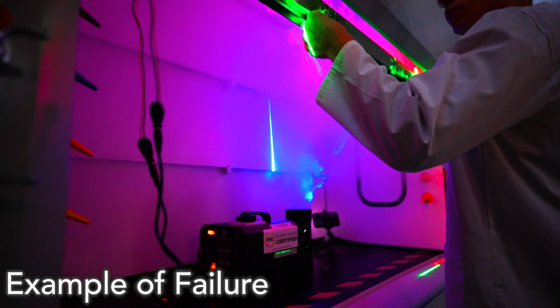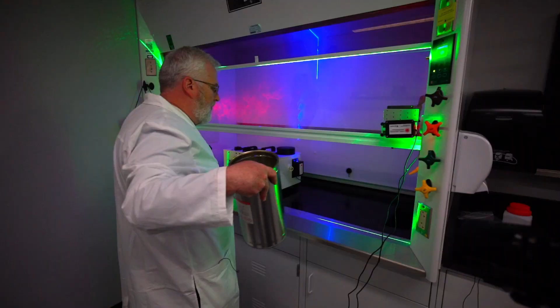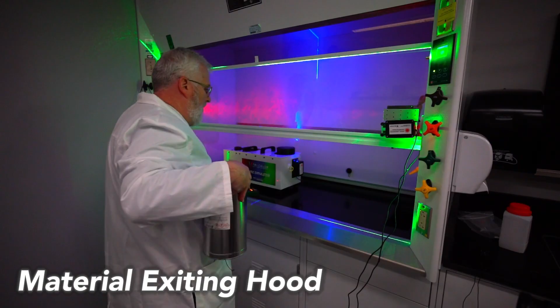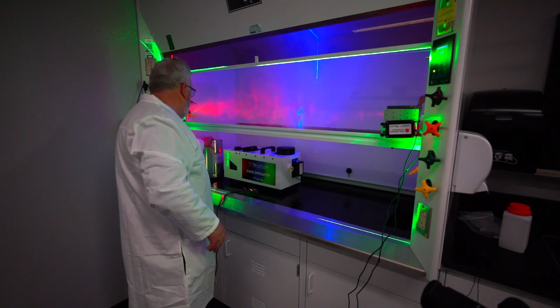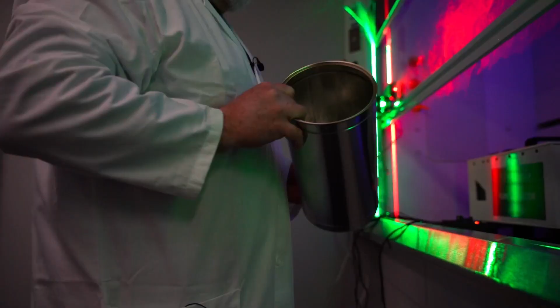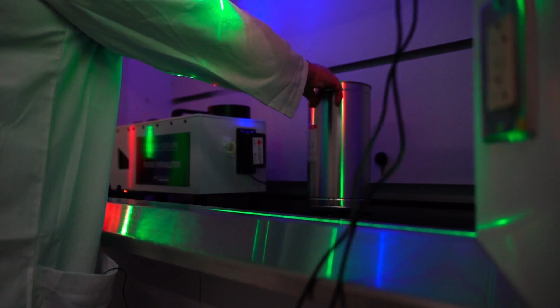Again, you might get a little better or a little different view if you stand to the side. This can be a tough challenge to perform because you just need to make sure that you have all of your Tri-Color laser cords pulled to the side and not tangled up with each other when you're raising and lowering the sash. Removing items from the hood can cause chemicals to follow that item out of the hood. For this challenge, you just want to grab any piece of equipment, set it inside the hood, and pull it out. See if you can get any green smoke to follow it. Moving large items will make a hood fail more so than moving small items like a beaker or a stand. But you definitely want to try a few different items and observe for any loss of containment.